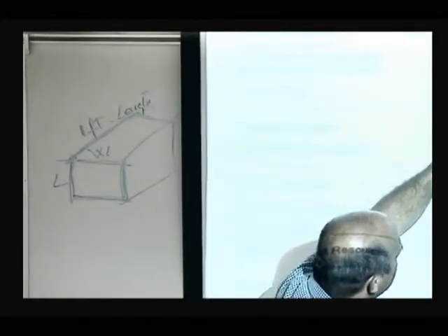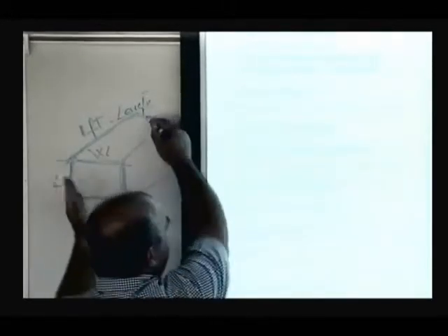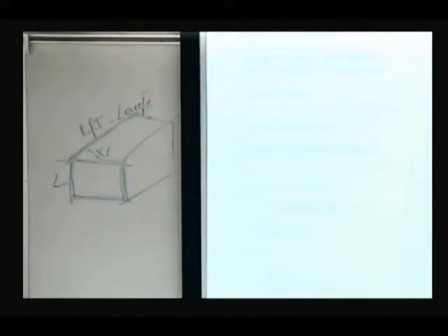So you add these two dimensions, that gives you the square feet per foot of linear duct, and then depending on the gauge that you have, it gives you the weight per foot in pounds.